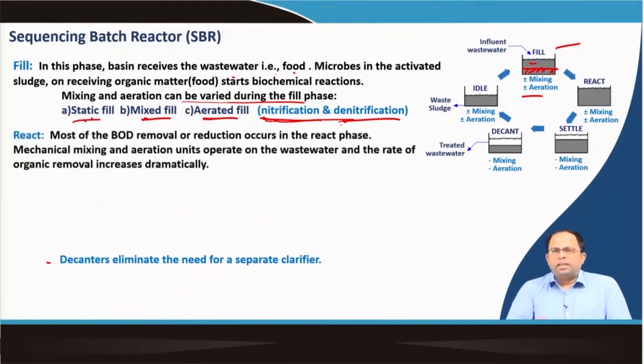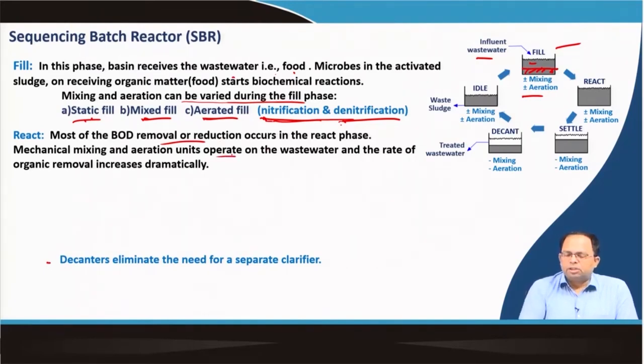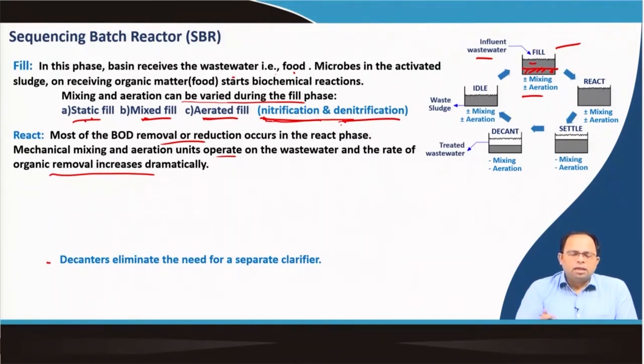In the react phase — after filling with influent wastewater — this is where most of the BOD removal or reduction occurs. Mechanical mixing and aeration units operate on the wastewater and the rate of organic removal increases dramatically, because more food is consumed and more bacteria are formed, which actually increases the BOD removal rate.